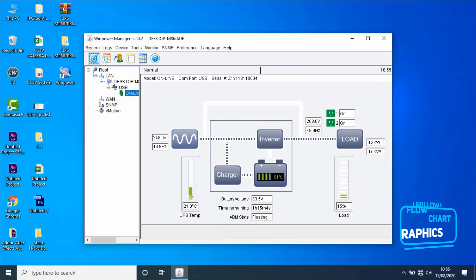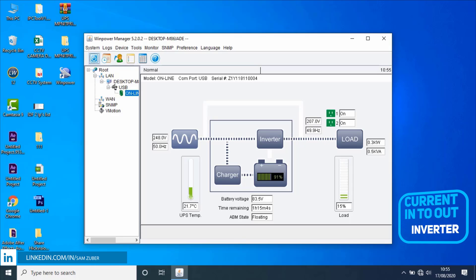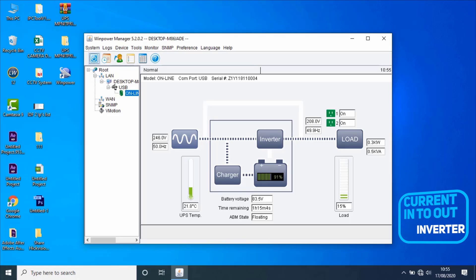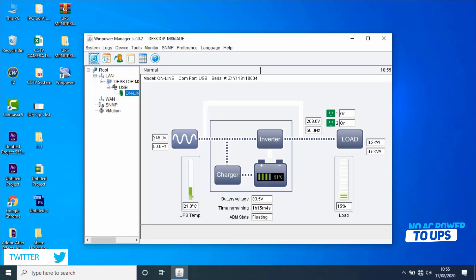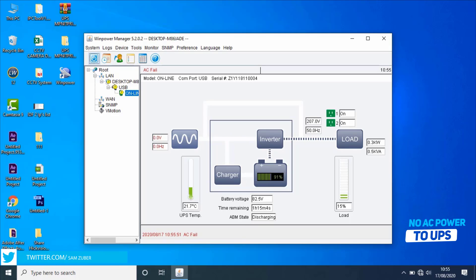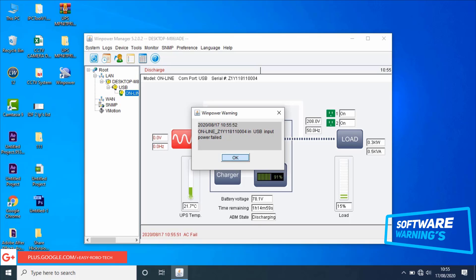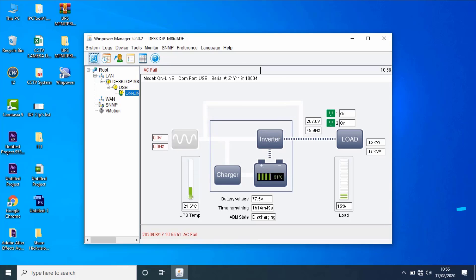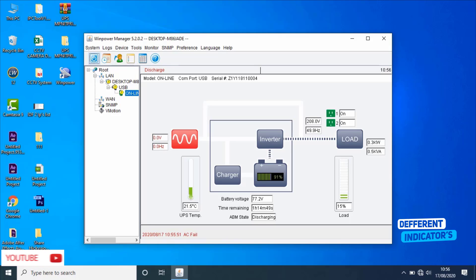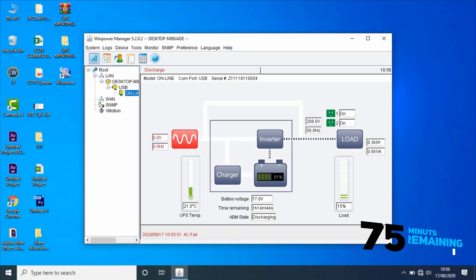If you observe the flow chart of the UPS, current is flowing from input to output via inverter. In between, charger and batteries are connected. Let's try turning off the input power for the UPS. Once the input power is off, software will give a warning message to the user. As you can see on the screen, it's showing a pop-up that says power failed, and the red indicator is indicating at the input of the UPS. The flow chart has changed — current is now flowing from battery to load, meaning the system is running on battery.